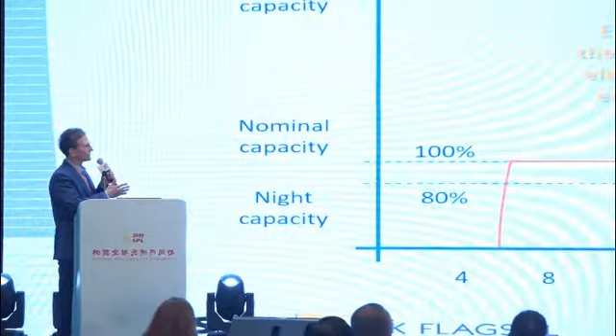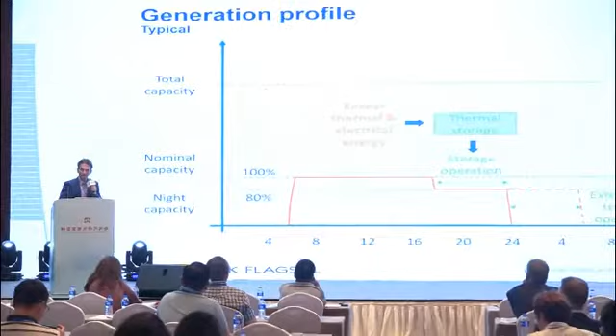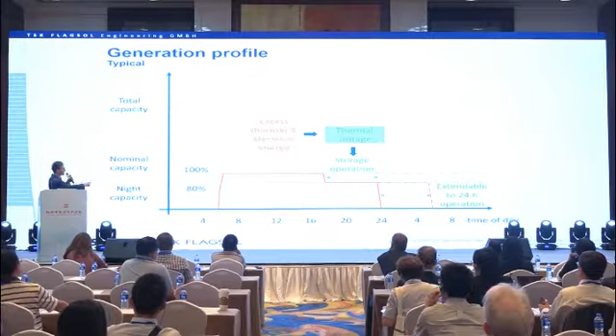Here you can see the dispatch profile of this particular plant. The orange line is the dispatch profile. Generation starts in the morning and is brought up to 100% of the nominal load, around 200 megawatt in this case. It stabilizes during the day, and when night operation starts after sunset, it goes down to 80% of nominal load, emptying the storage over 5 hours. This 5-hour limitation is specific to this project, because Morocco has an evening peak until midnight and doesn't need the power afterward. That was a project restriction, but in theory you can design the storage to continue operation until the next day without turning down the plant.